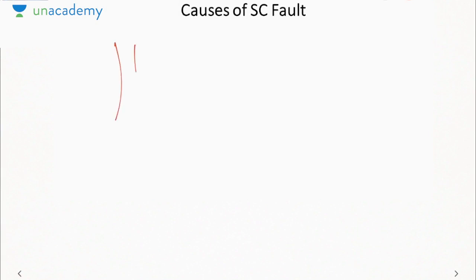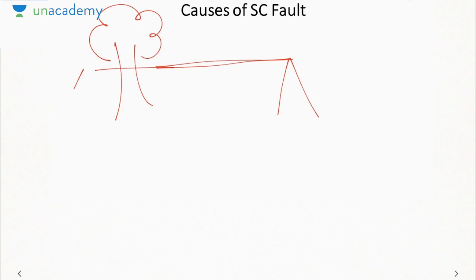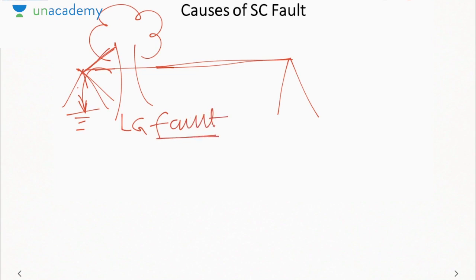Now suppose there is a tree, and there is a transmission line that is going from a tower. What happens if a tree branch falls on the transmission line? Then it will connect the line to the tower, so the current will flow from the line into the ground. That will act as an LG fault where one line is grounded. So that is one of the most common causes: when a tree branch falls on a transmission line, a line to ground fault occurs.